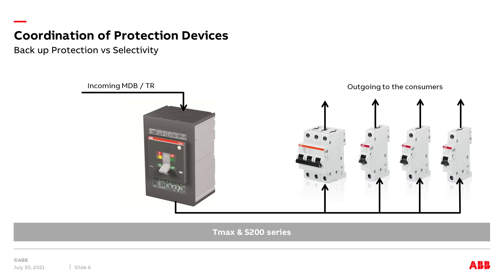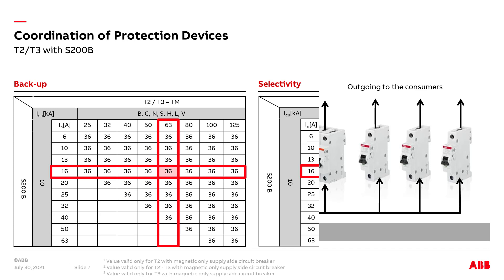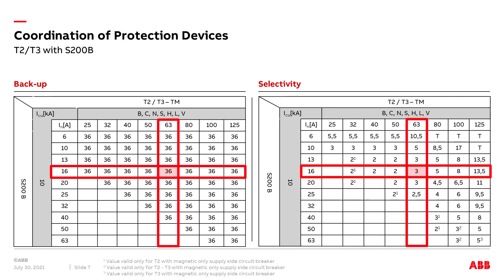Let's change the S800 to a T-Max. This is a very common combination in buildings; however, it has some disadvantages, especially in final distribution. The T-Max needs more space inside the enclosure, and you may need special internal assembly modules. Using the same characteristics — 63 amperes for the incoming device and 16 amperes for the outgoing device — this combination provides the same backup protection of 36 kilo amperes. The selectivity level is a bit higher at 3 kilo amperes, so the T-Max would not trip below 3 kilo amperes short circuit in the downstream branch.